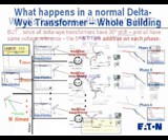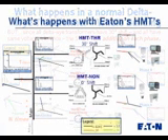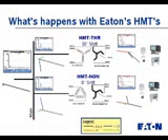When looking at what occurs when you add that same type of load to HMTs, we can see clearly what's going to occur. There are two main types of HMTs in use in standard commercial office, school, medical, and casino environments. That is the HMT-THR and the HMT-NON. The HMT-THR is a 30-degree shift, similar to the standard delta-Y. The HMT-NON has a zero-degree shift. It's these differences in shifts that allow the harmonic currents to be canceled.